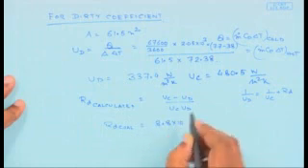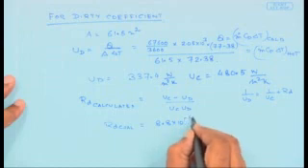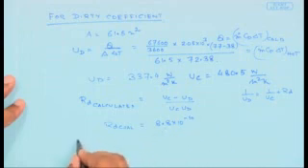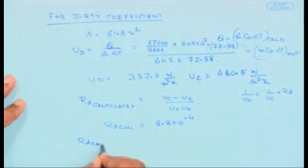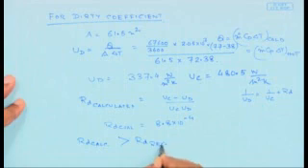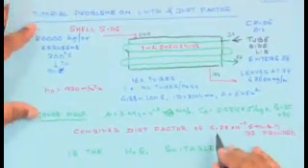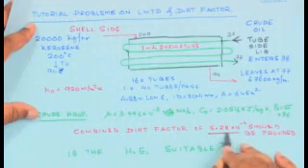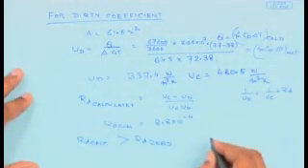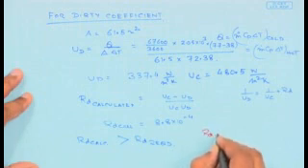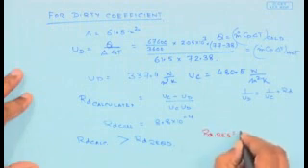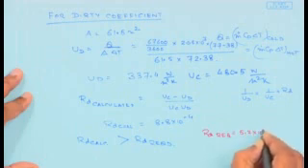8.8 into 10 to the power minus 4, and we can see that this Rd calculated is greater than the Rd which is the required one. The Rd required is provided at the beginning in the statement of the problem, that the combined Rd factor should be 5.2 into 10 to the power minus 4. So, Rd required is 5.2 into 10 to the power minus 4.